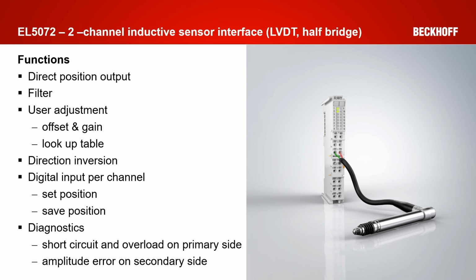Furthermore, different diagnostics options are available. Besides the EtherCAT communication diagnostics, some product diagnostics is also available. For example, if you have 2 probes and one of them draws too much current, so you get a short circuit on the excitation source, it can be displayed. Also on the measuring side, we have some error detections. For example, if the input signal level is too high, this could be because the parameters were set in a wrong way or because of some cabling error, it's also displayed.